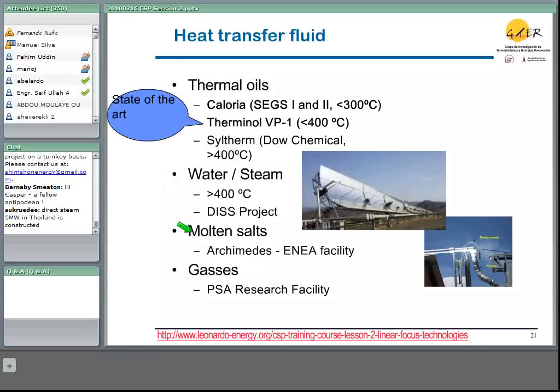The main problem with molten salts is that the melting point, or freezing point, is quite high, and you have to make sure the molten salts never freeze in the tubes, valves, pumps, or other components of the molten salt system, otherwise you get in trouble. To avoid the freezing, there are different ways.